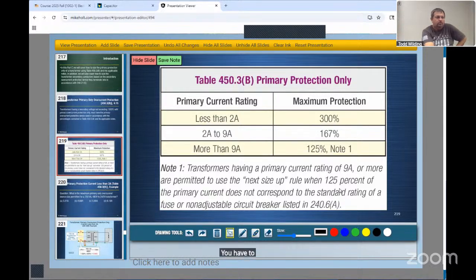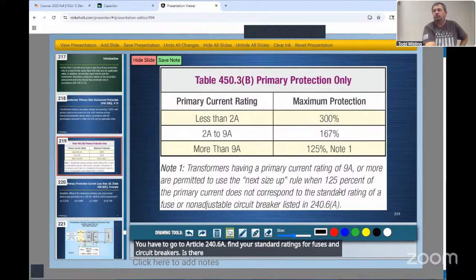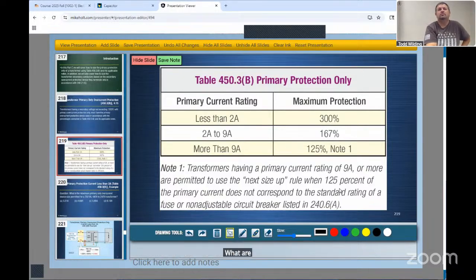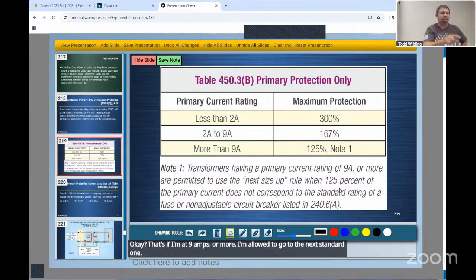You have to go to 240.6(A) and find your standard ratings for fuses and circuit breakers. Is there a 32 amp size fuse or circuit breaker? What are my standard sizes? 30 and 35, right? I'm right in the middle. So according to that, I'm allowed to go up to 35. That's if I'm at 9 amps or more, I'm allowed to go to the next standard one. If I do not have 9 amps or more, I have to go down. Okay?